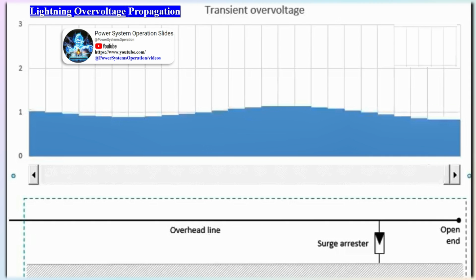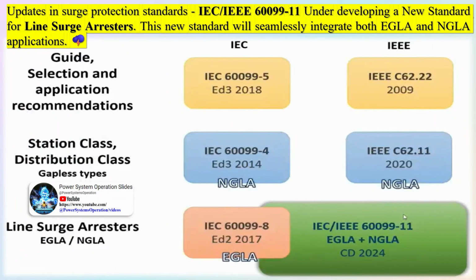They are less commonly used than metal oxide surge arresters but offer some advantages, such as a higher energy absorption capability. The type of surge arrestor used will depend on the specific application and the requirements for surge protection in that application. It is important to select a surge arrestor with appropriate voltage and current ratings to ensure effective protection and reliable operation. Surge arresters are used in a variety of applications to protect power distribution networks and equipment from overvoltage transients. Some common applications of surge arresters include substations.